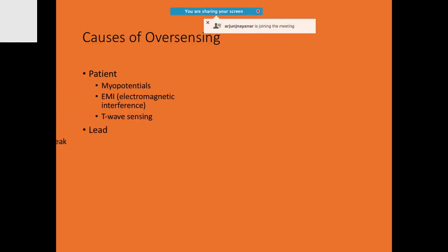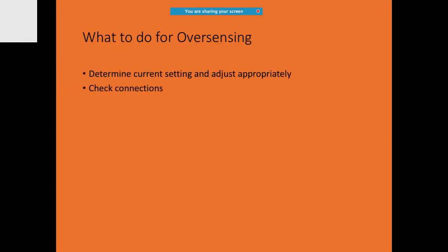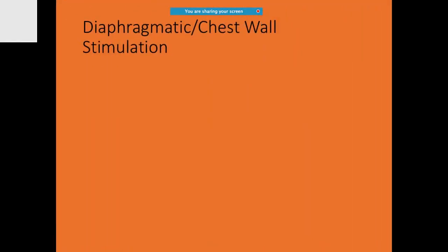Myopotentials, electromagnetic interference can cause over-sensing. For the pacemaker as well, you may not have programmed it well. There's the phenomenon of crosstalk. If this problem is happening, you should check for the connections and adjust the blanking periods.